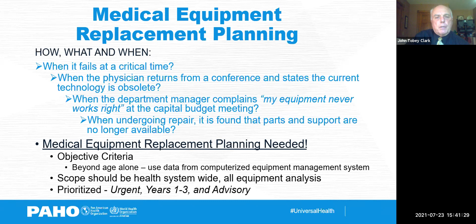You want to have a plan. That plan should use objective criteria, data from your computerized maintenance management system. It should cover the scope of the health system, and it should prioritize that replacement. So the factors important in replacement are maintenance. Do the manufacturers still support the product? Are the service costs advancing? Are the failures increasing? Is there poor documentation? On the safety side, are there unresolved safety issues, recalls that haven't been resolved, continuous user errors, lack of essential safety features? Otherwise, the equipment may not be standardized. If you get new equipment, it may reduce your expenditures. That's on the other side of the coin. High wear, obsolescence, age, those are three factors that certainly have to be considered.